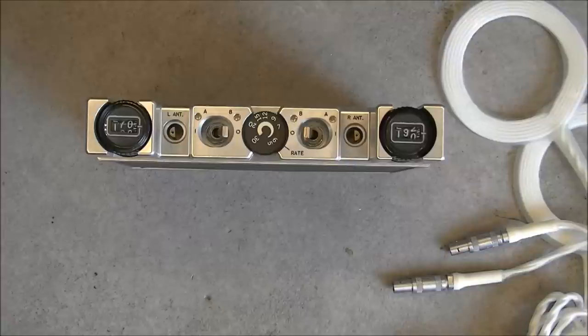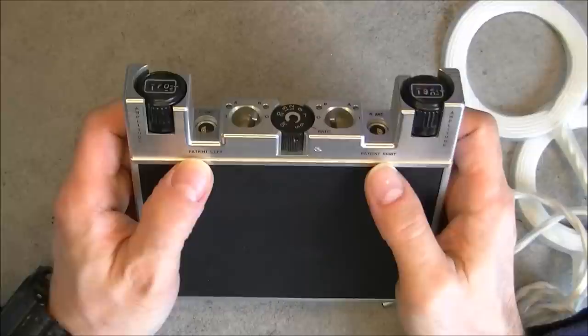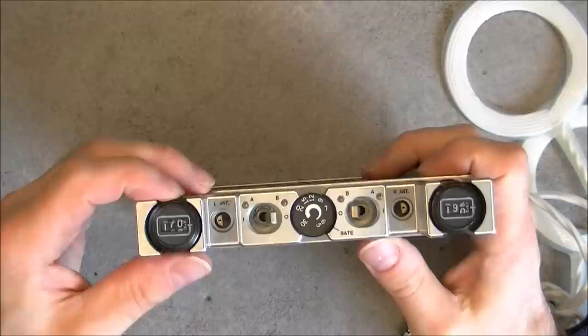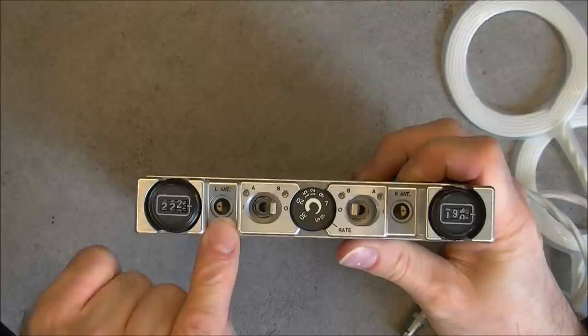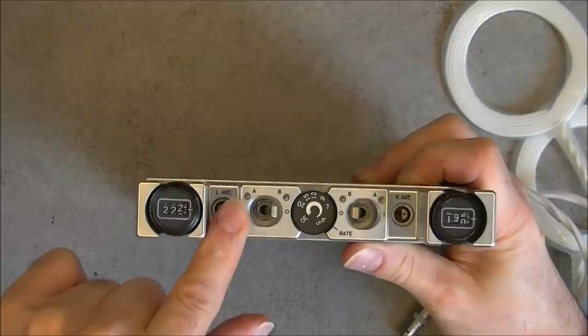So there are two pairs of similar controls, one for left side and one for right side of the patient with an amplitude setting button containing an integrated dial. We have plug for the antenna. We have on off switch for each side. Antenna LED and battery status LED and one single rate control.